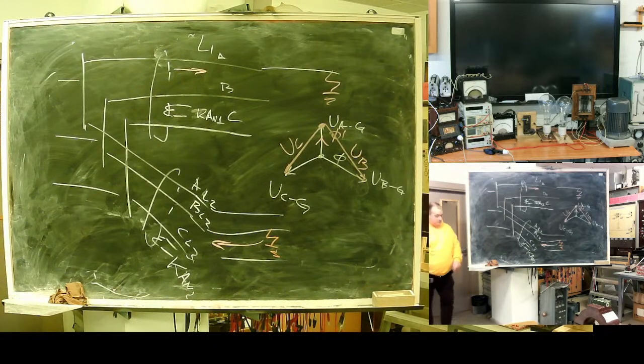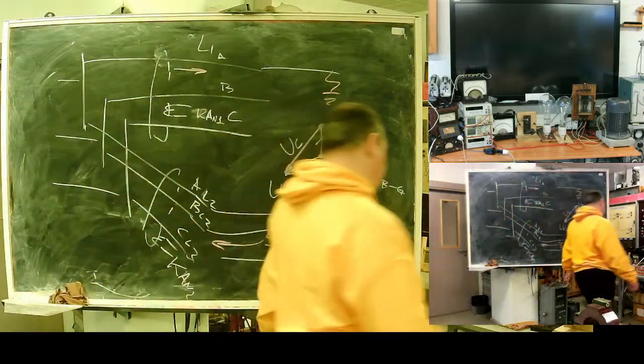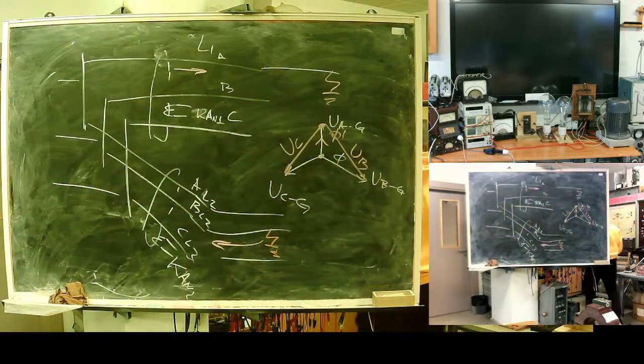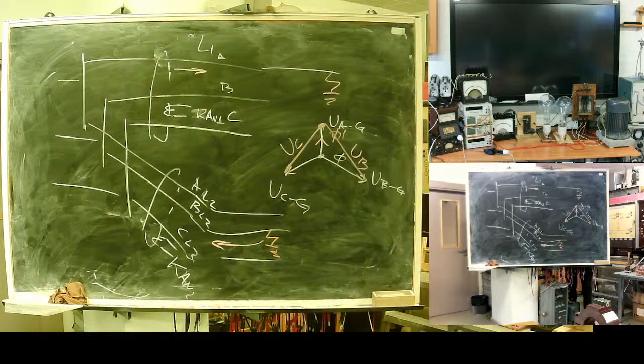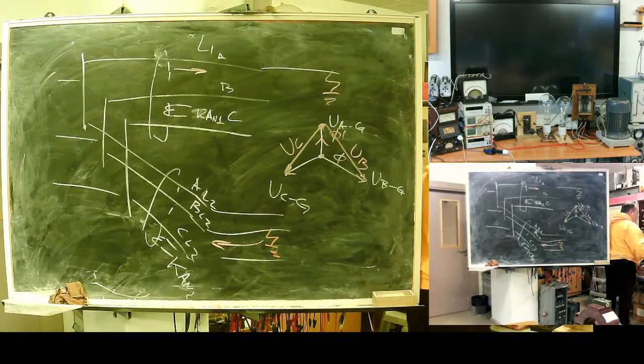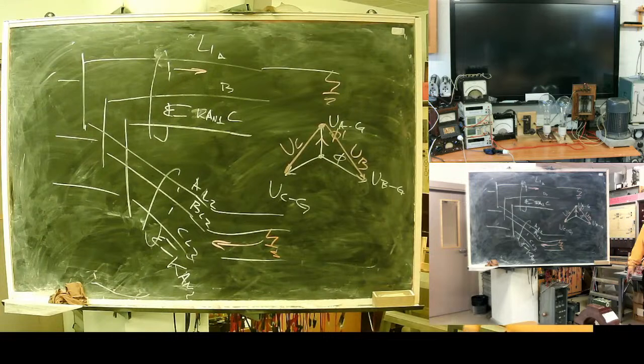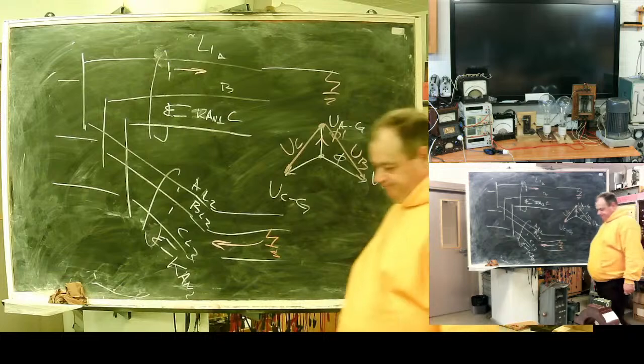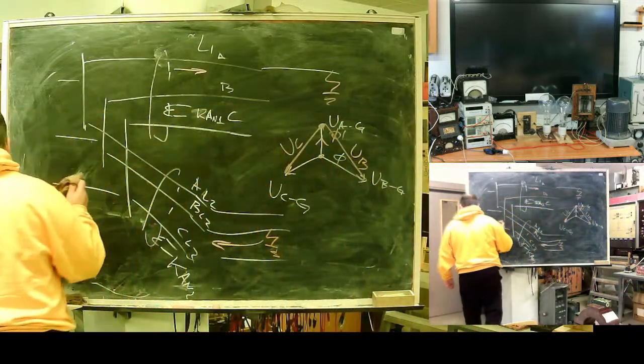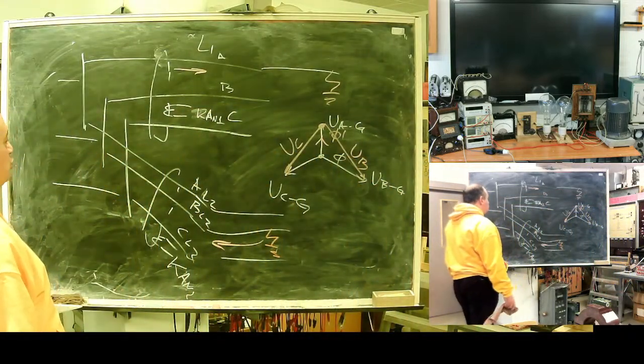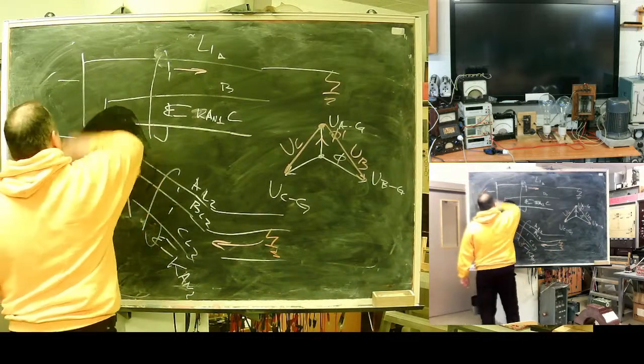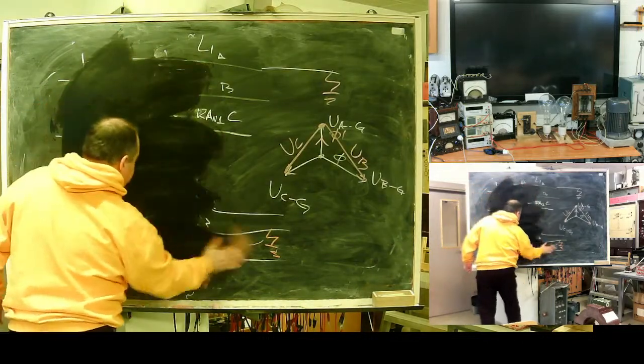Problem of double faults. You need a very high... your inputs should be able to withstand very high current rating. Sensitive, but with very high possible current. It's problem number one. Problem of double fault. Problem number two is so-called intermittent arc.